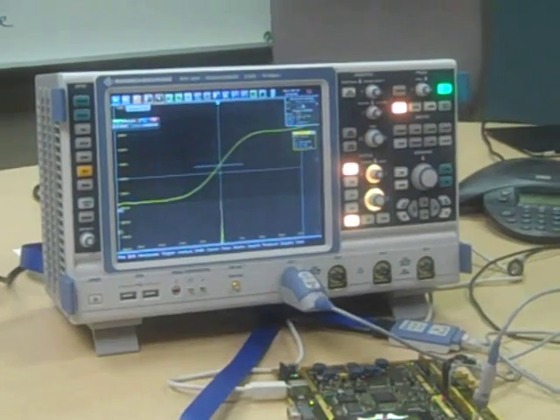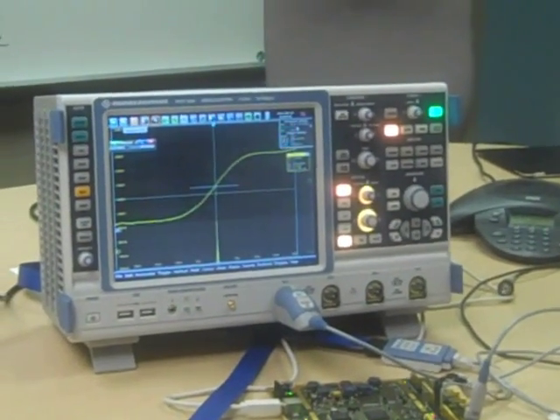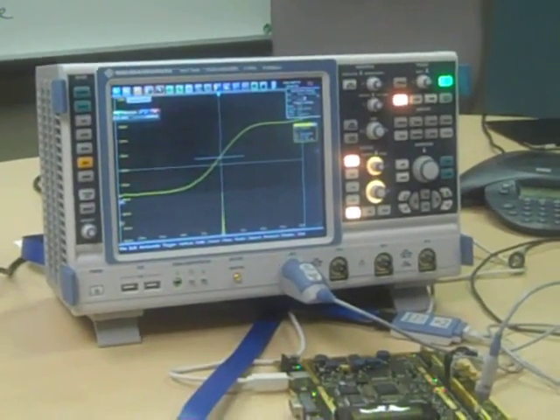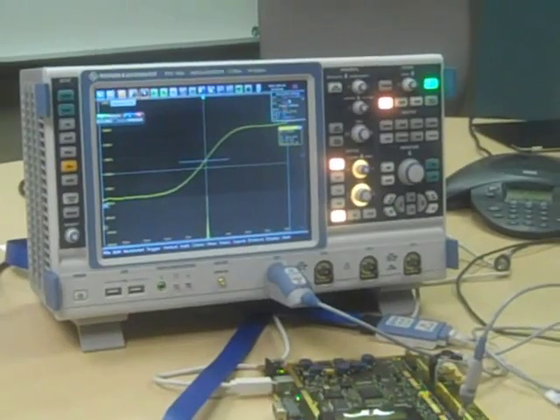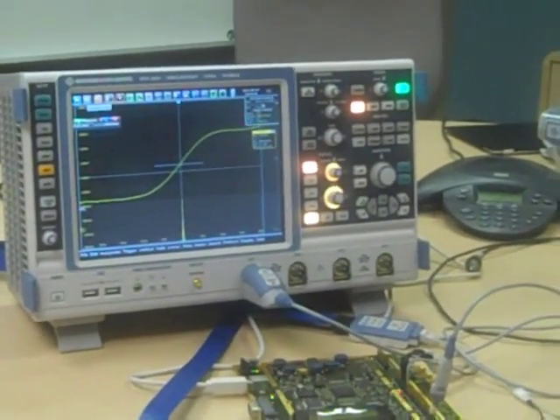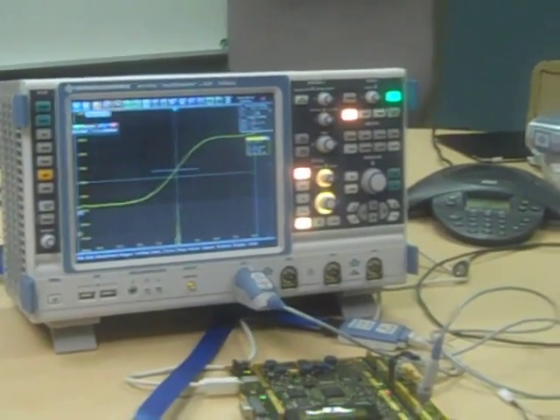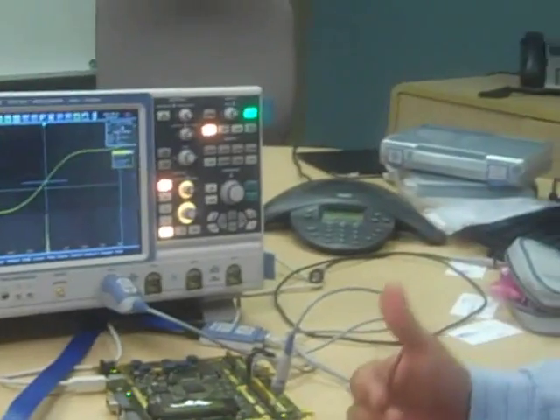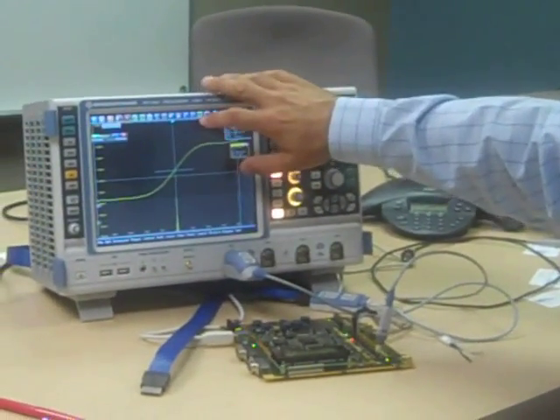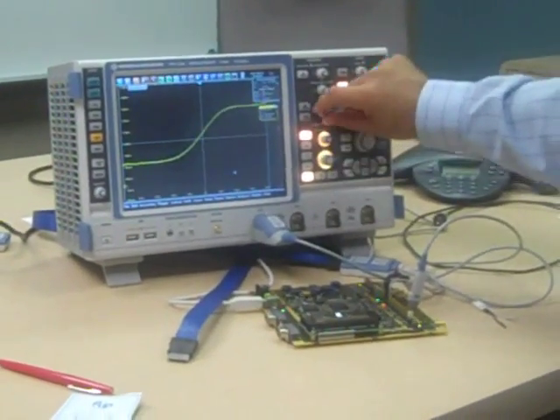We're going to see it's very small. In this case, it's about 116 picoseconds RMS. The reason for that very low trigger jitter is the digital trigger, and in fact, that jitter that you're viewing is really the residual noise in the front end of the scope operating through the slope of that signal and not actually the trigger jitter at all. So there's really zero trigger jitter contributed here. Let me turn off that histogram and the measurement, and we'll go back to full screen display.